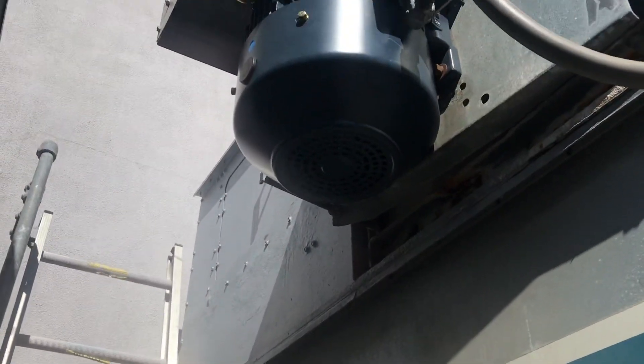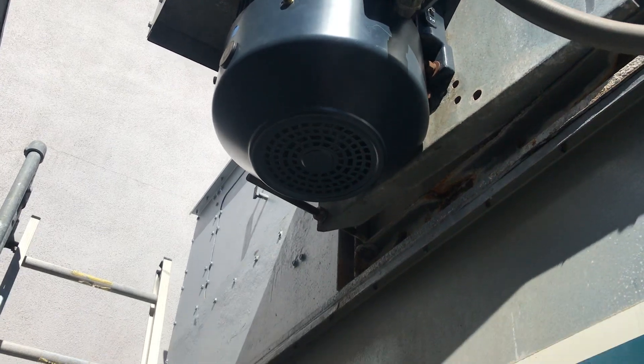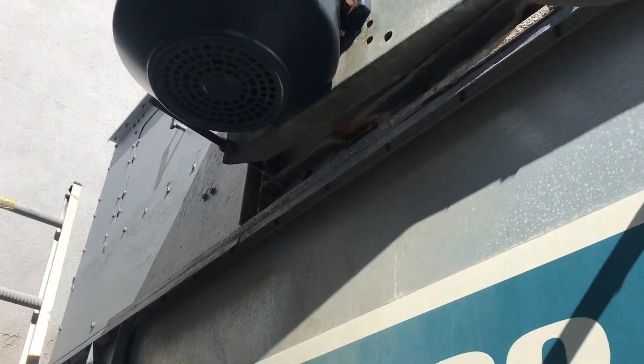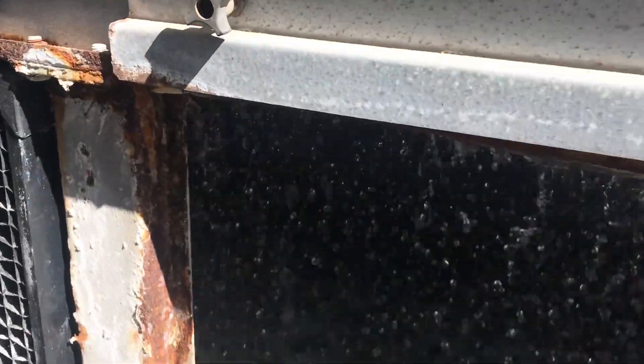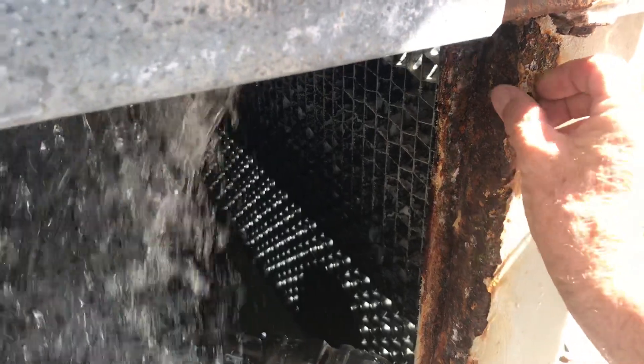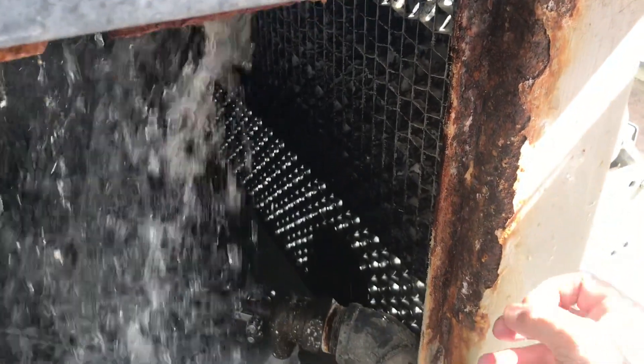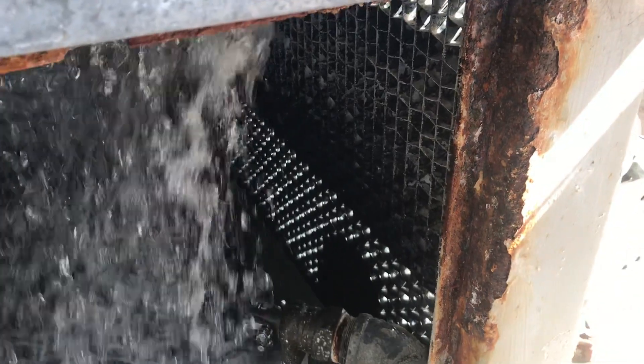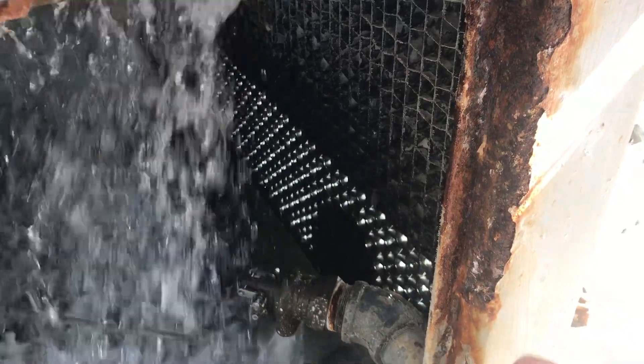We replaced this motor — it's a 15 horsepower fan motor, already replaced. The guys did a pretty good job. So I'm going to go ahead and give him a price to replace that float and make some recommendations on this rust. You can really see it's breaking away. Maybe in the wintertime we'll try to do a coating on it and get the rust treated. It's just really breaking apart.